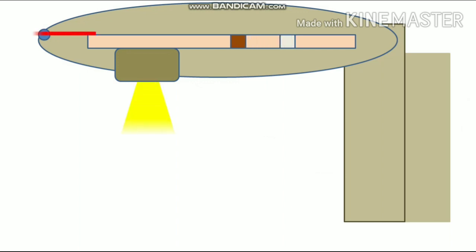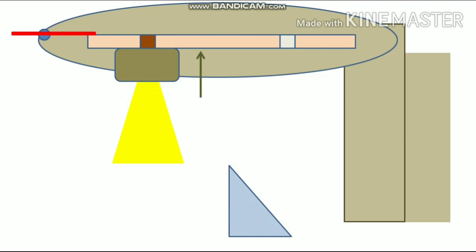In a teletherapy unit, we set the irradiation time in the primary timer. The source moves from the fully shielded position to fully exposed position, delivers the dose for the set time, and returns back to its shielded position. While coming to the beam on position, the output or the exposure rate starts rising from 0 to a steady state. Suppose the time required for this is tau 1.